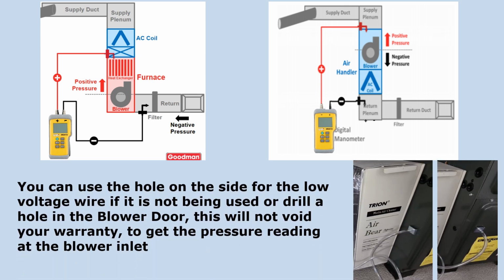You can use the hole on the side for the low voltage wire if it is not being used, or drill a hole in the blower door. This will not void your warranty to get the pressure reading at the blower inlet. But on these two examples, the one on the left, the furnace, you notice that the pressure tip is pointing into the airflow, meaning that the airflow is going in the opposite direction of the tip.